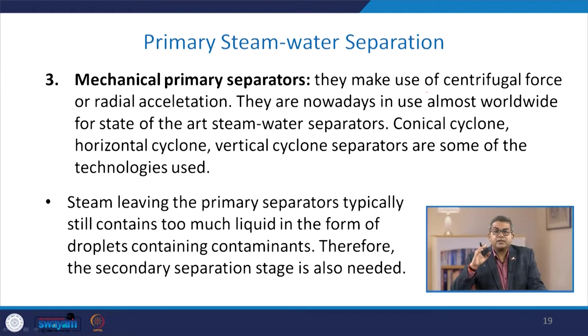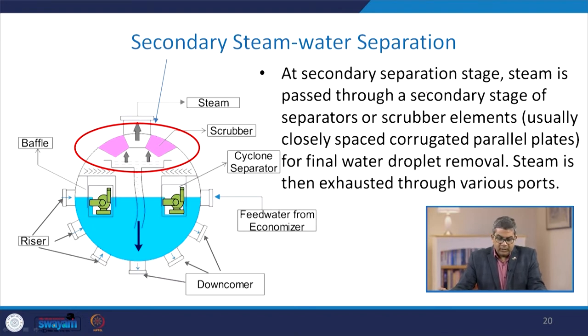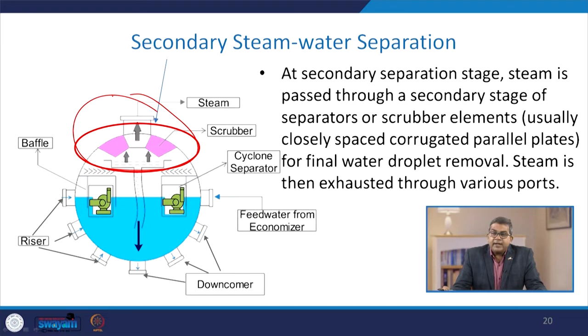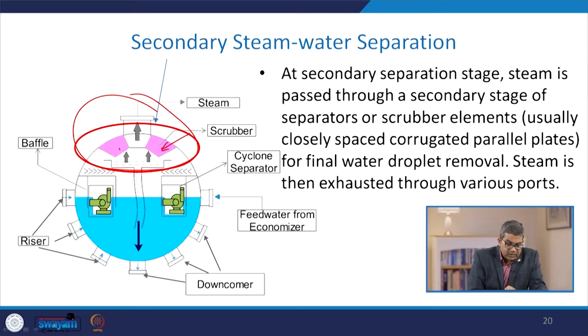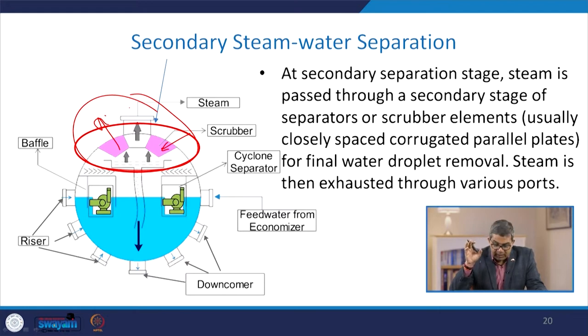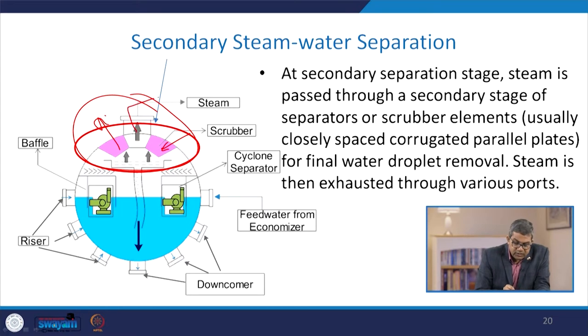Steam leaving the primary separators typically contains too much liquid in the form of droplets containing contaminants. Therefore, a secondary separation stage is also needed. At the secondary separation stage, steam is passed through a secondary stage of separator or scrubber — usually closely spaced corrugated parallel plates — for final water droplet removal. Steam is then exhausted through various ports.